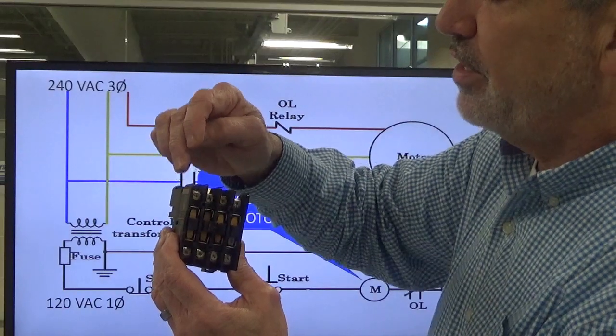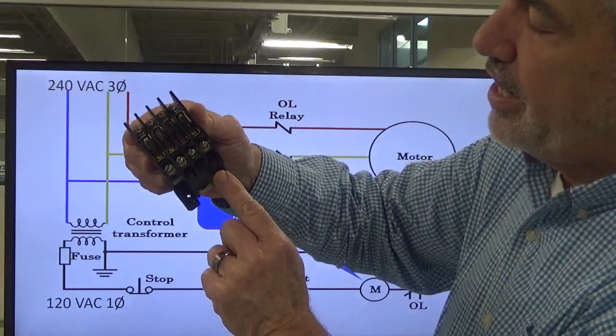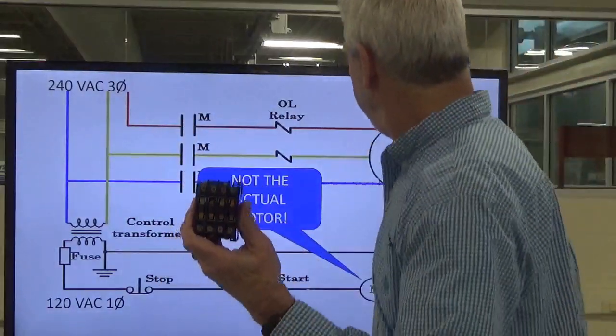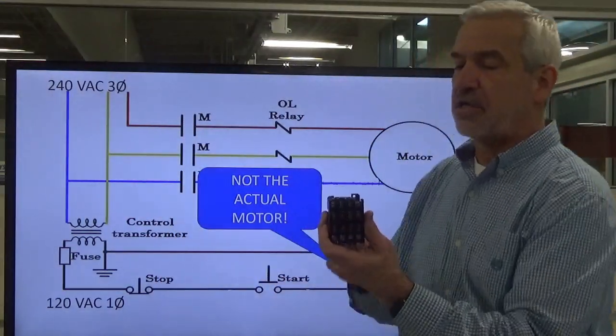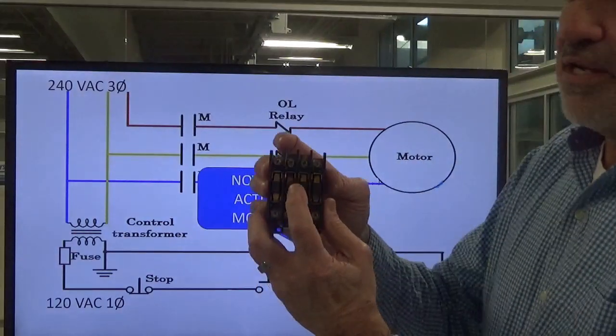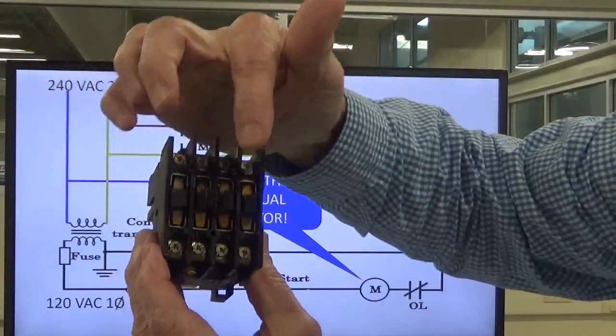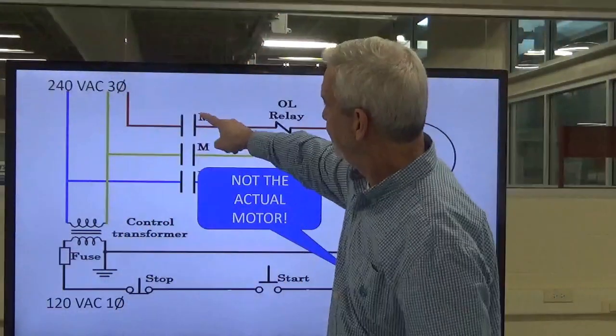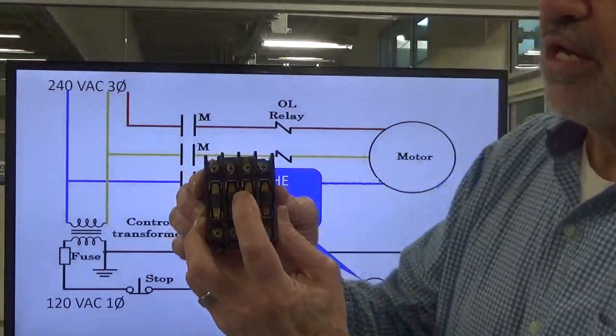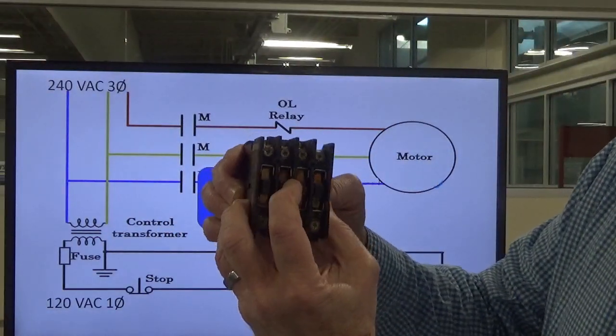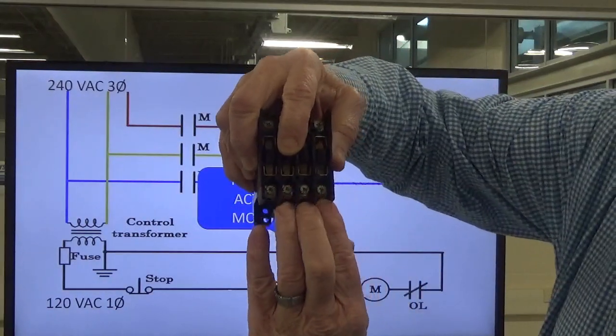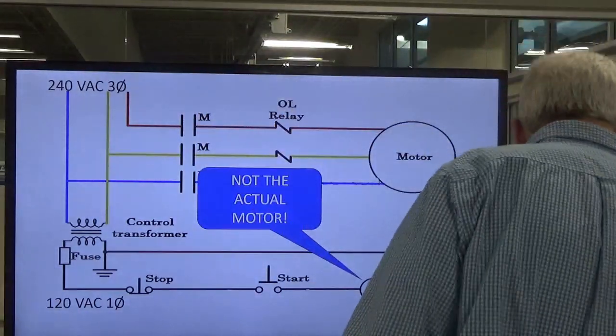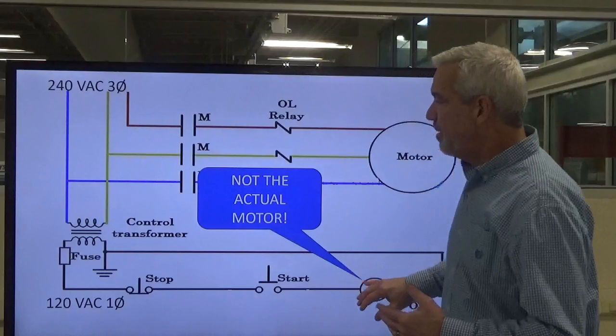Again, we're going to put voltage on our coil right here. Here's our positive, 120 going in, and here's our neutral, 120 going out. That would be through here, okay? So when we energize that coil, we create that magnetic field. Boom, it pulls it, and these little copper bridge pieces right here, these are contacts. These are normally open contacts. Again, these are the contacts right there. So when we energize it, we close the contacts. The voltage is resting right here, and then when we close it, it gives it a path to exit the starter and on out to the motor. So that's how the motor starter works.